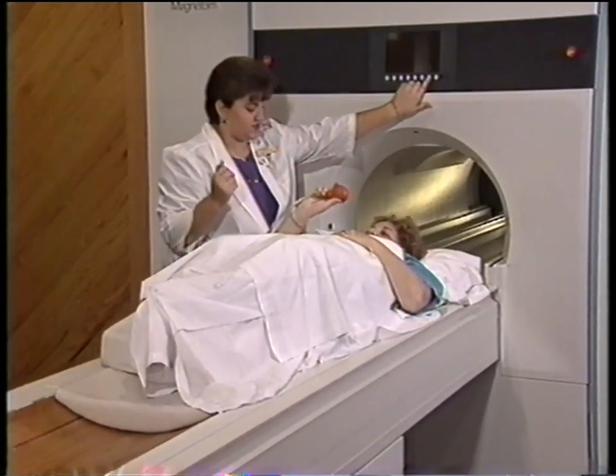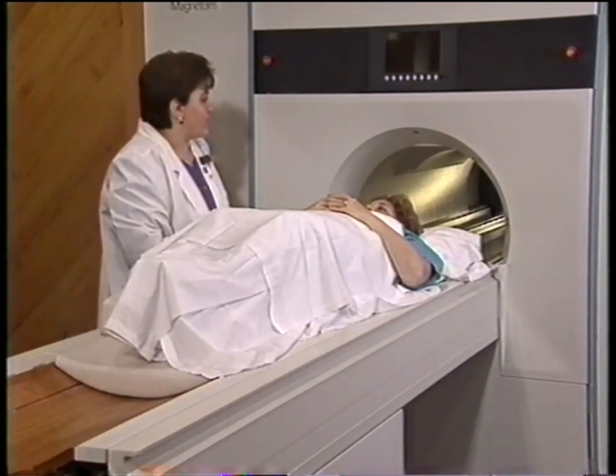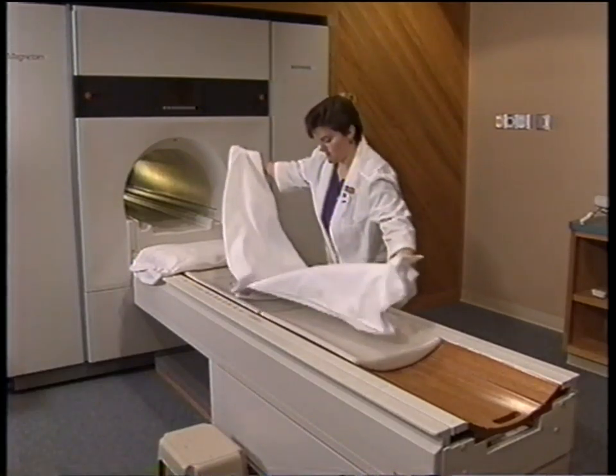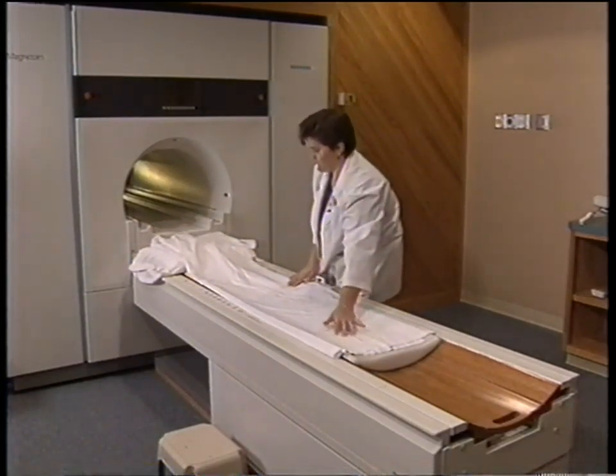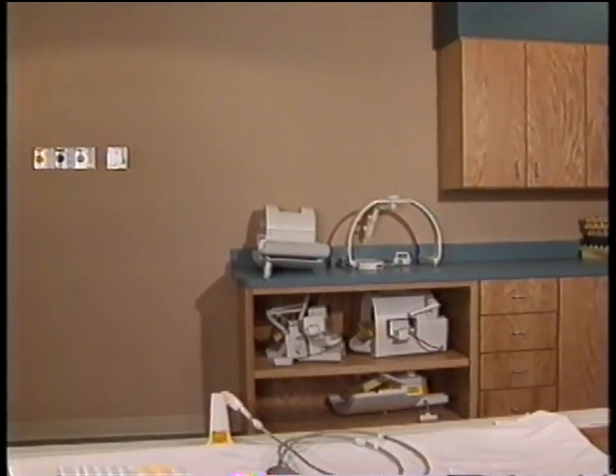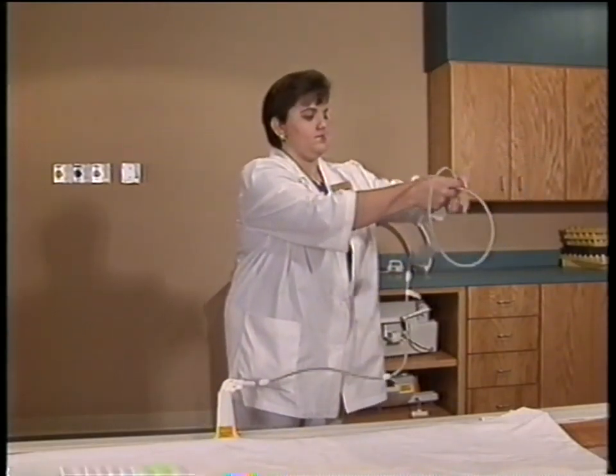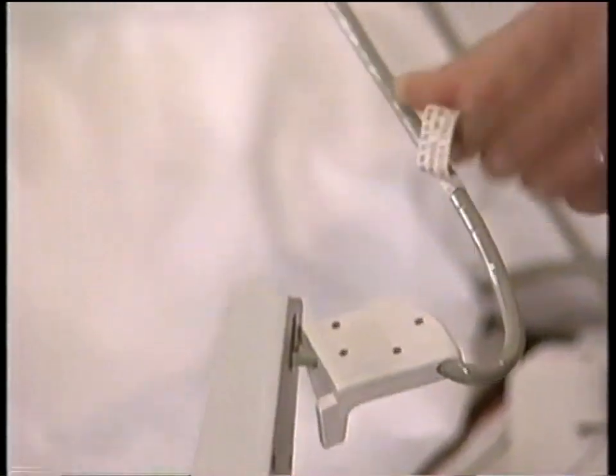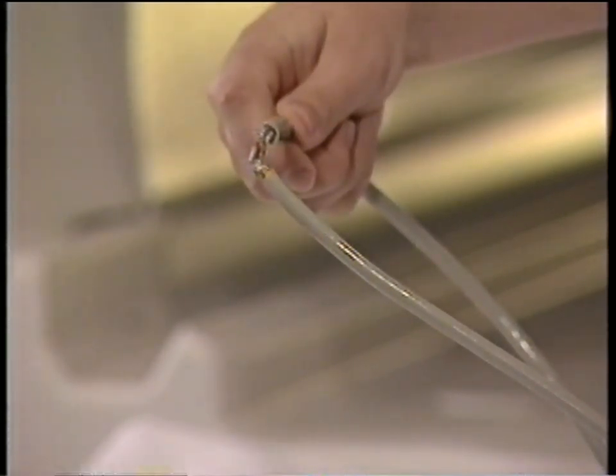Communication with the patient is a vital safety consideration — make sure you stay in touch using the intercom throughout the examination. Exercise appropriate caution when moving the patient into and out of the bore. It's always recommended that you place some sort of covering between the coil and the patient. All Siemens coils purchased for use with the MR system are designed for use in a specific way. Using the coils in ways not recommended by Siemens could result in harm to the patient or the coil itself — in fact, all MR equipment should only be used in ways recommended by the manufacturer. Always make sure that the cables of the coils as well as ECG and peripheral pulse cables are not touching the patient and are straight, not twisted around themselves or each other. If you notice a rip or tear in the casing of the cable, do not use the coil and immediately bring this to the attention of your Siemens authorized service engineer.